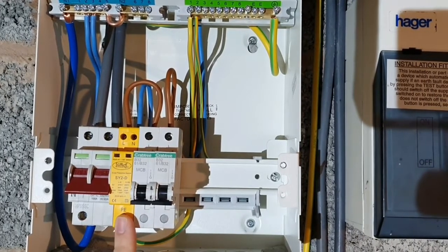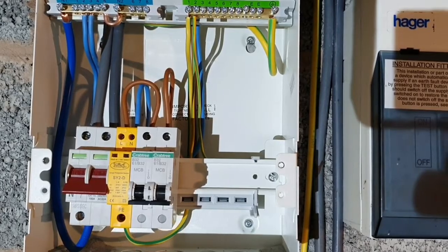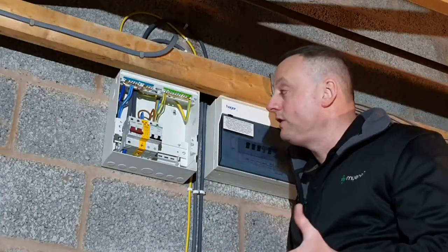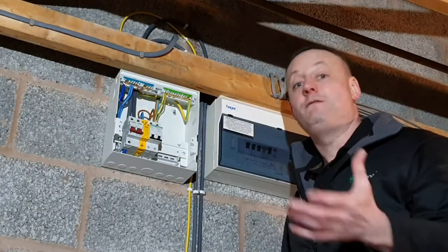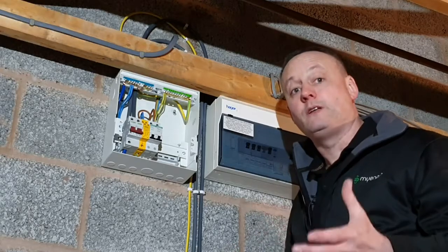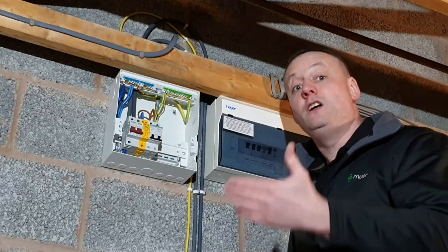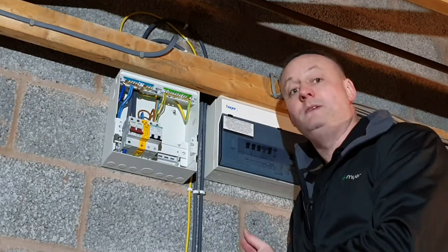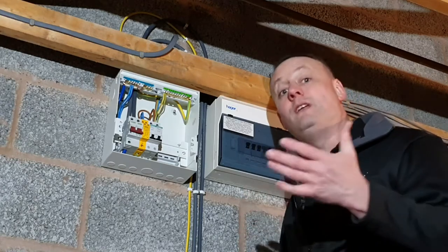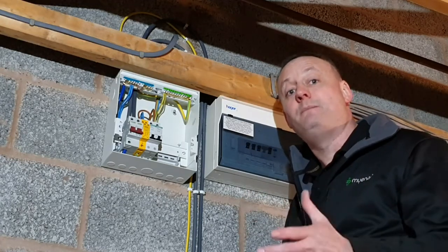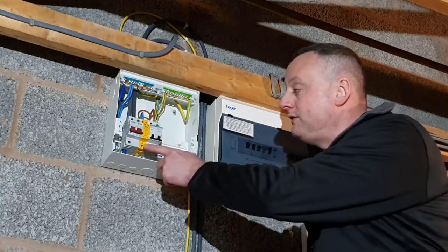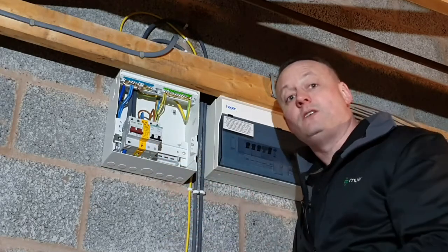What have we got installed here? Yeah, the customer decided that it would be good for them to have a surge device inserted. We're going to be plugging in potentially a £40,000 car full of electronic components. In the event of a surge in the installation, we wouldn't want that to be fed down to the car. There's loads of electronic components also within the Zappi 2 that would be protected by the surge device being inserted here. So they decided to have that device inserted.